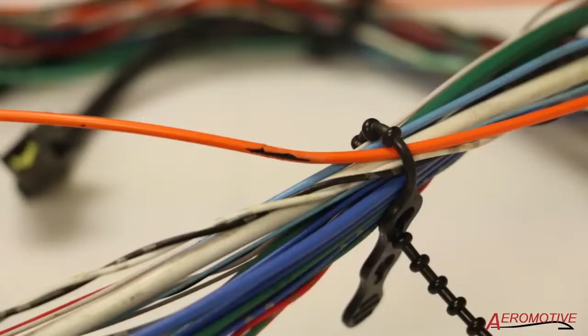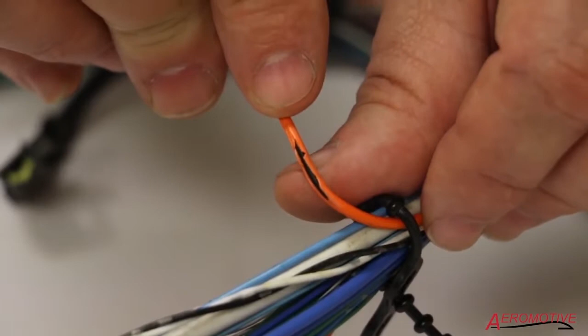We have an assembly here that has some fiber optic damage. The first question is, how did we know this was fiber optic cable? Well, it's the color—this orange to mustard color is standardized. So whenever you see this in a harness assembly, you have to immediately think this is fiber optic cable. Here you can see there's a little bit of a nick in it. Didn't take much, but luckily it doesn't look like it reached down into the fiber optic cable itself—it really just hit the outer coating. So it's pretty much intact, but not worth taking the risk.